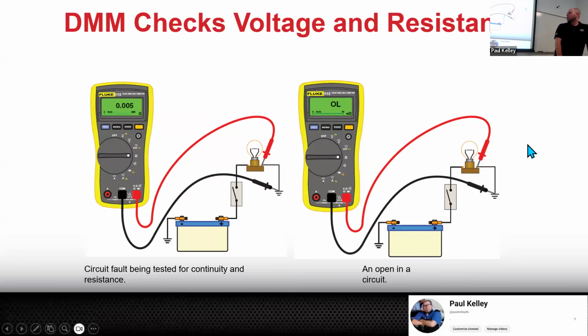On this picture, what are we measuring? We're measuring resistance of what - it's resistance of a component. What is between the red and black lead? The ground wire, exactly. So if you thought the ground wire was no good, you could usually test it with voltage, available voltage, or voltage drop. But if you want to measure resistance, you just put whatever you want to measure between the red and black lead, put it on ohms, and it'll give you a number. The resistance of a wire should be pretty much 0 - maybe 0.2 is what the meter would read, but pretty much 0.